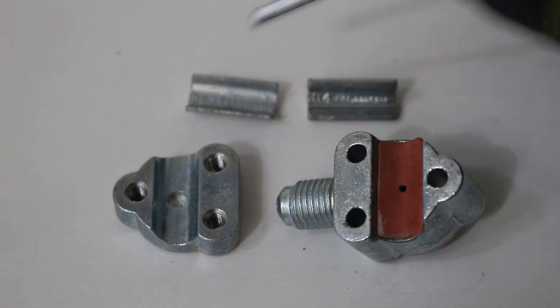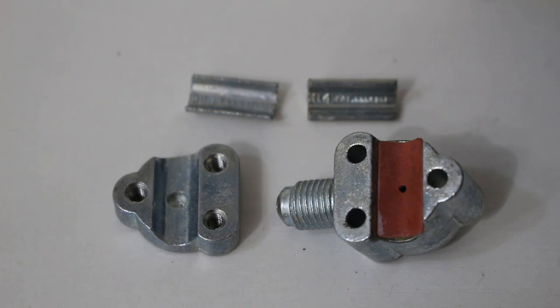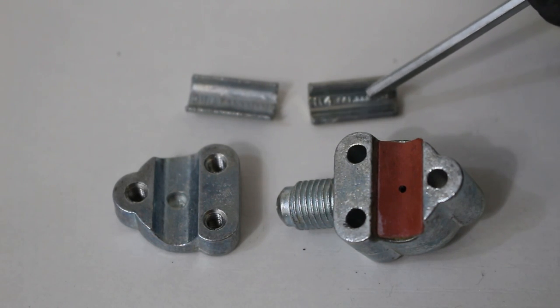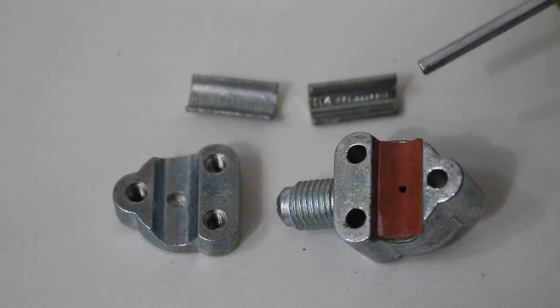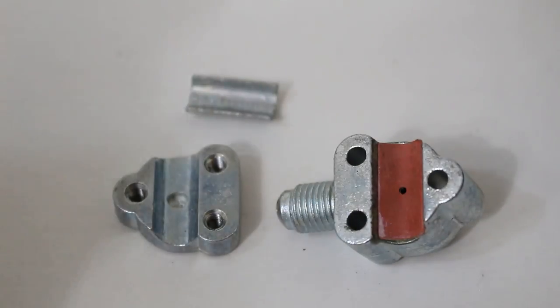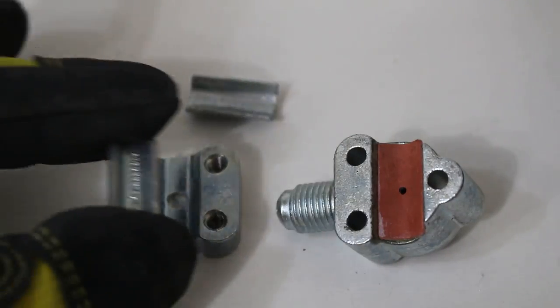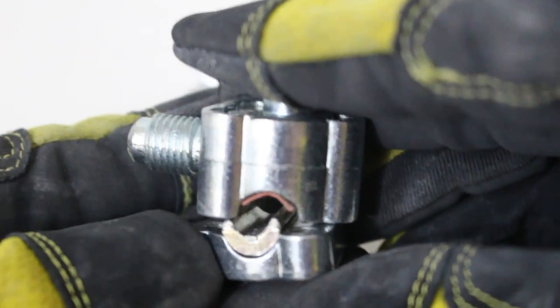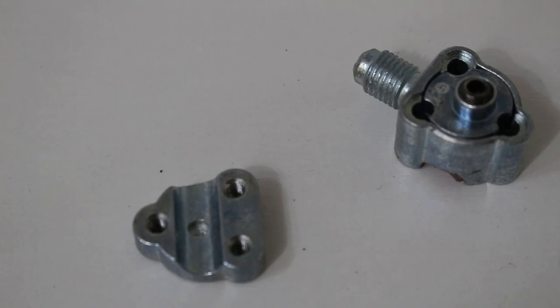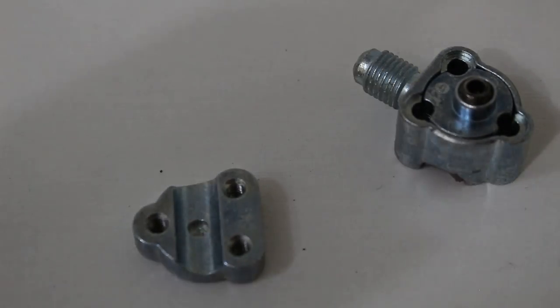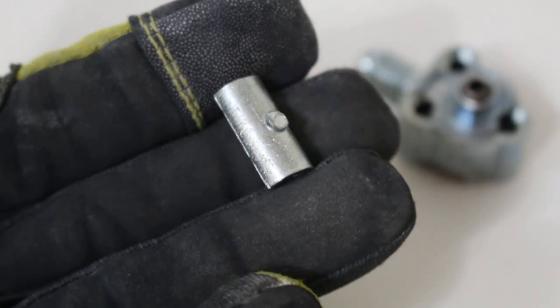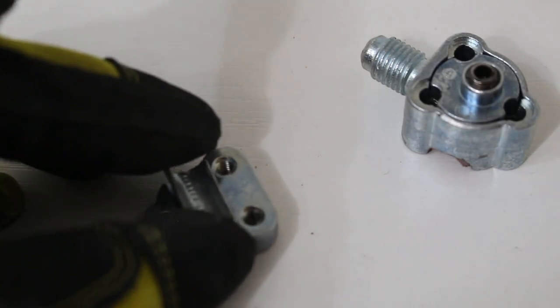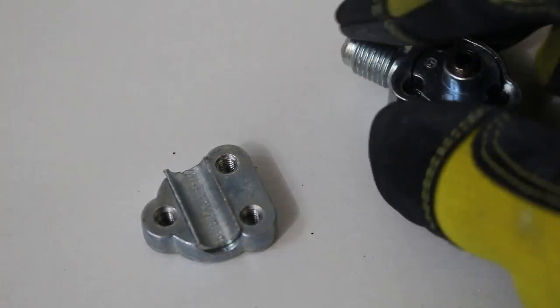All right, so now we have opened up our valve, and here are two adapters. So, if we're using a 5/16th pipe, we would use this adapter. If we were using a 1/4-inch pipe, we would use this adapter. If we're using a 3/8" pipe, we don't use any adapter. But let's say you had a 1/4-inch adapter. You would put that piece in here. Once that adapter is on, we can then close this valve. Next, the same principle, if you were using a 5/16th pipe. As you can see, there is a small little notch here. And you would match that up with the notch right there. Just drop it in. It basically just acts as a filler. So, you can use this for the correct size pipe.